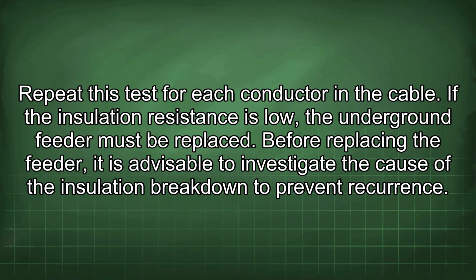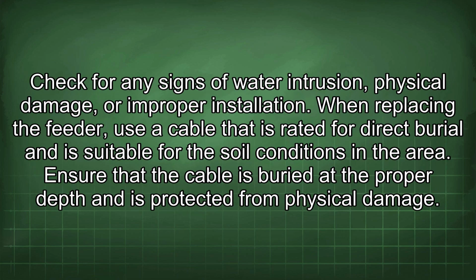Before replacing the feeder, it is advisable to investigate the cause of the insulation breakdown to prevent recurrence. Check for any signs of water intrusion, physical damage, or improper installation. When replacing the feeder, use a cable that is rated for direct burial and is suitable for the soil conditions in the area.